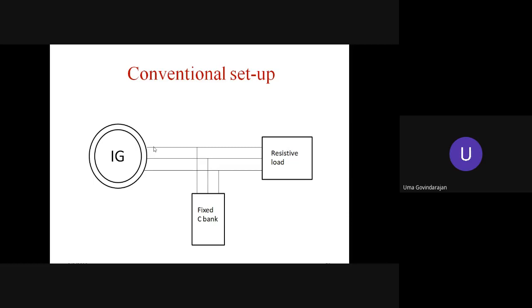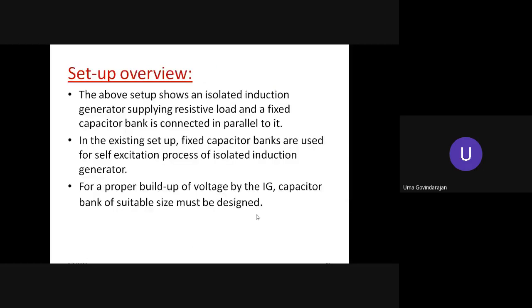So the capacitor bank supplies some magnetizing current. Based upon past experiments conducted on the machine, it will have some residual magnetism. With that residual voltage, the capacitor bank will energize initially. It will start supplying the current. The machine will start rotating slowly, and hence the machine will start generating to its full potential. So that's how the induction generator works.